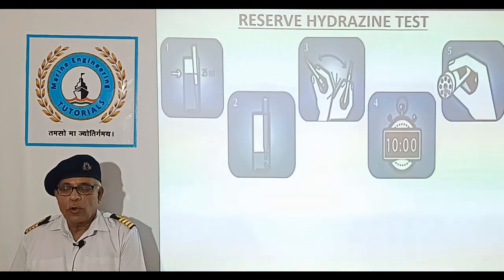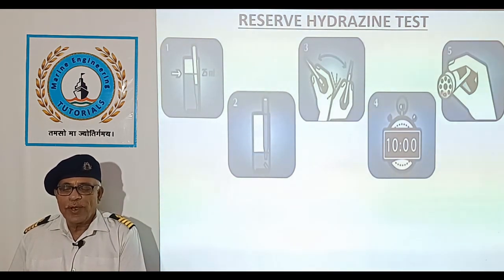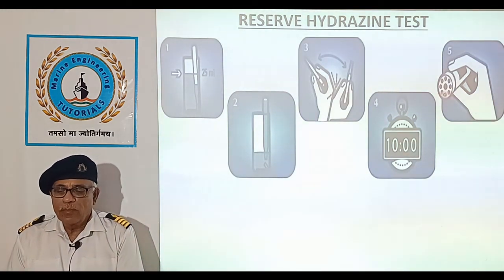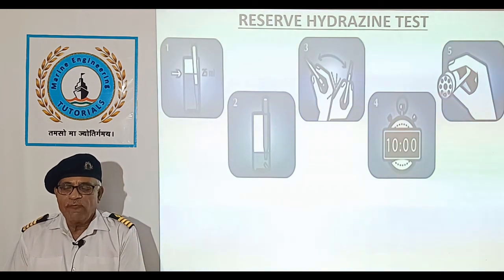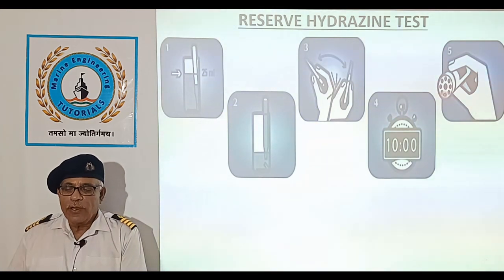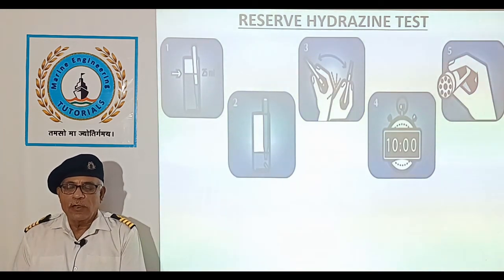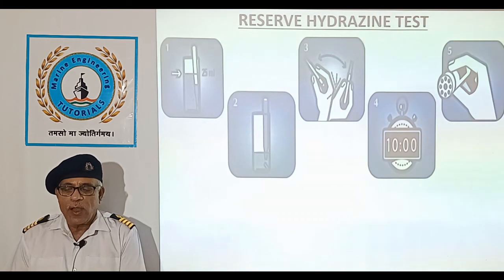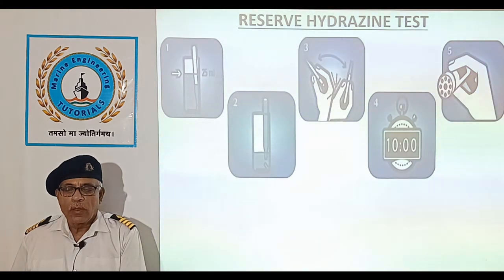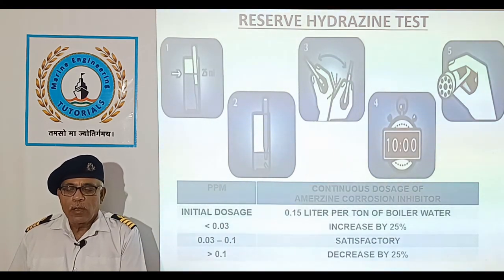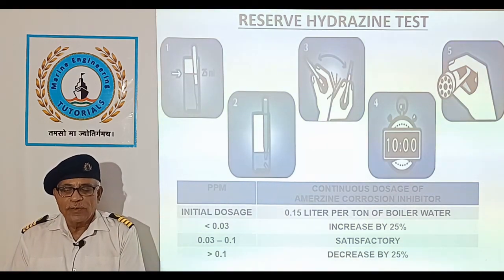Place the corrosion inhibitor ampoule flat and downwards in the center tube of the comparator. Direct the comparator towards a source of bright white light. Hold the comparator in a nearly horizontal position and rotate it until the color standard below the ampoule shows the closest match. Record the results.